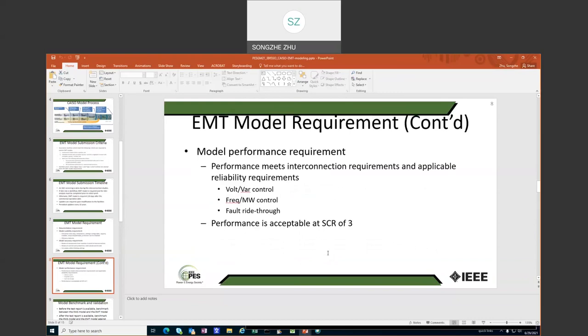Then it comes to the model performance requirement. The performance requirement is to check the performance against interconnection requirements and applicable reliability standards. So typically those requirements include volt-var control performance requirements, and frequency control requirements like FERC Order 842, and ride-through requirements. Those requirements are typically specified in the generation interconnection agreement. They are also based on various reliability standards and FERC orders.